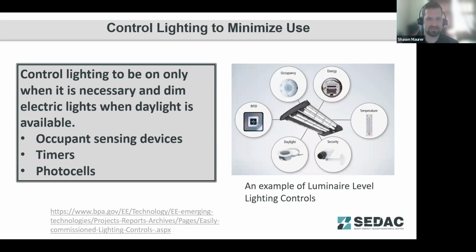Controlling lighting to minimize use. Showing an example here of luminaire level lighting controls, but you could also do distributed controls in the buildings. But you want to make sure lighting's only on when necessary, when needed by the occupants, and that it has the ability to dim and control so that occupants have the ability to fine tune the conditions to what's comfortable for them. So making sure also that these controls are going to provide kind of fail-safe operation. Someone can't leave the lights on by accident. The light's not going to stay on 24/7 for some reason.